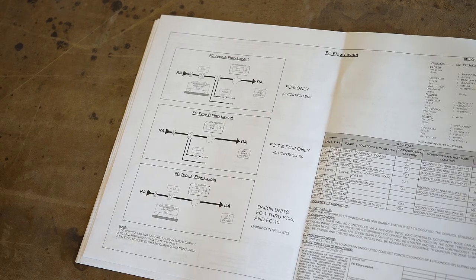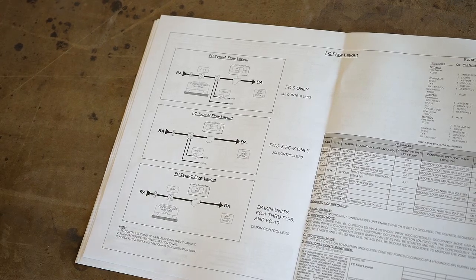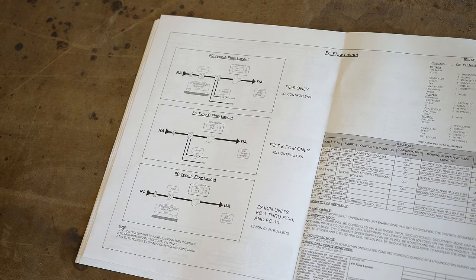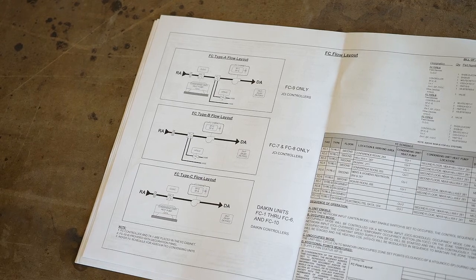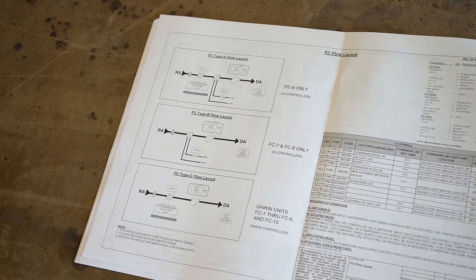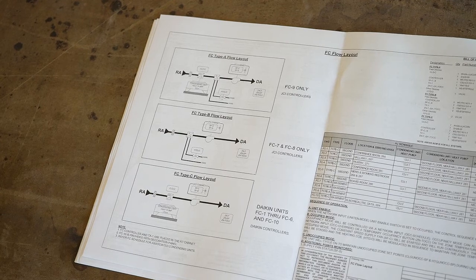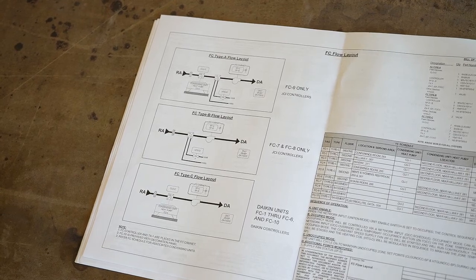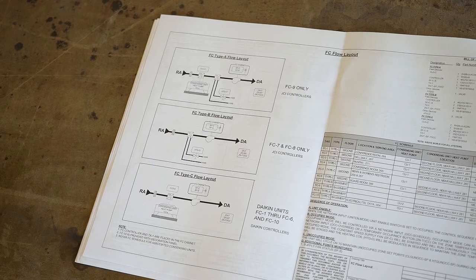Okay, so those are daisy chained in on our SA bus, which is different than our trunk we were talking about earlier. And then we're pulling the temperature in from the stainless steel plate, and we're pulling the set point in from the other temperature sensor in the registration area. So you could find the lobby cool because somebody put a candle over near the stainless steel plate and a printer under the thermostat in the registration desk, and we're artificially thinking it's warmer than it is.